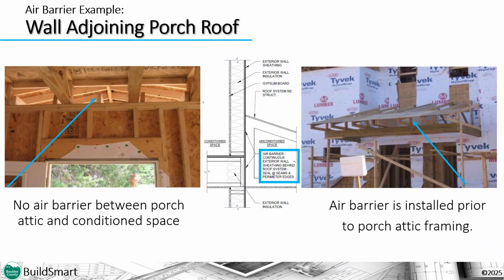Here are examples of continuity and lack of continuity, and who is responsible for 90% of the air barrier installation details. Well, it's the framer, when it happens well and when it doesn't happen well. The picture on the left shows what happens when proper sequencing of the installation of materials is not followed. There is no air barrier between the porch and the rim joist between the first and second floor. Once drywall is installed, the problem won't be visible, but outside air will be able to mix with the conditioned air inside the home. In addition, it will be difficult to insulate the rim joist at the porch connection. These problems can lead to hot and cold spots and comfort complaints, as well as a higher energy bill and non-compliance with the code.